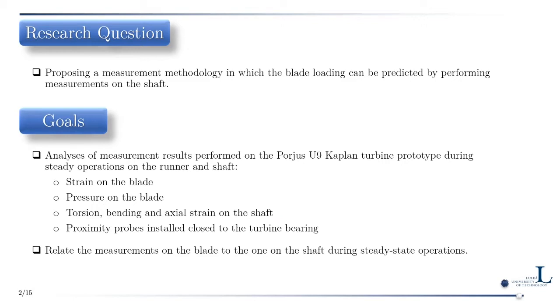This project was initiated to propose a measurement methodology in which blade loading can be predicted by performing measurements on the shaft. The goals include analyzing measurement results from the Porjus U9 Kaplan unit during steady-state operating points on both the runner and the shaft. Various sensors were used on rotating and stationary parts: pressure and strain gauges on the blade, torsion, bending, and axial strain measurements on the shaft, and proximity probes near the turbine bearing. The goal was to relate blade measurements to shaft measurements during steady-state operations.